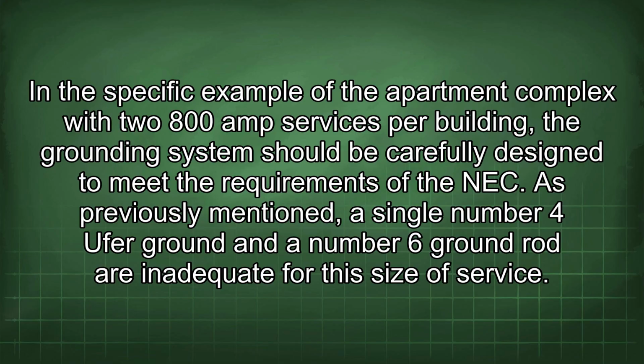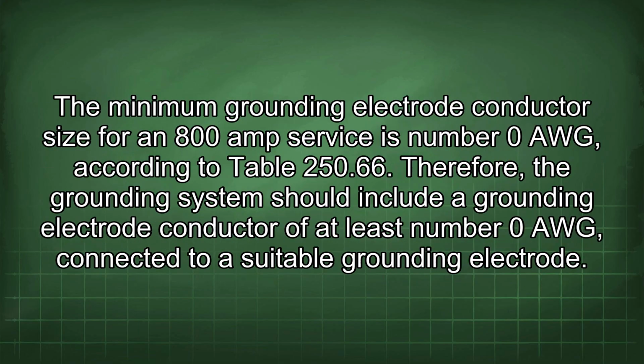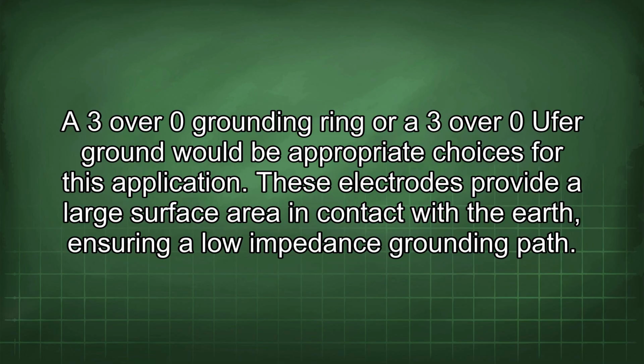As previously mentioned, a single number 4 Ufer ground and a number 6 ground rod are inadequate for the size of service. The minimum grounding electrode conductor size for an 800 amp service is number 0 AWG, according to Table 250.66. Therefore, the grounding system should include a grounding electrode conductor of at least number 0 AWG connected to a suitable grounding electrode. A 3/0 grounding ring or 3/0 Ufer ground would be appropriate choices for this application.